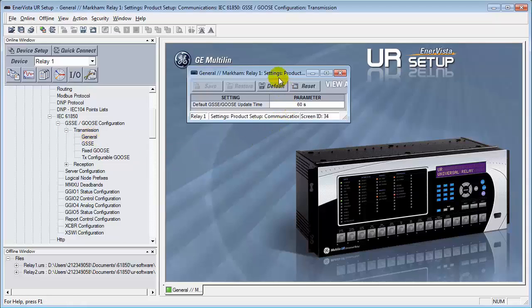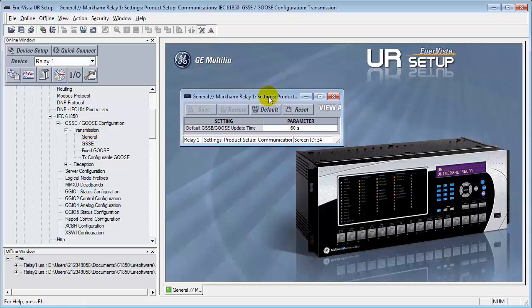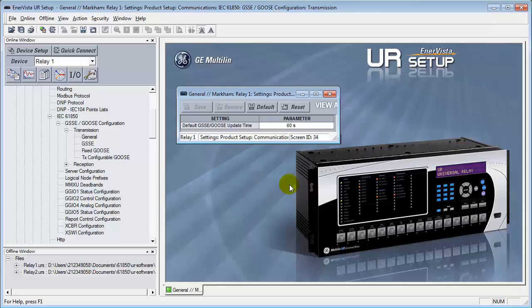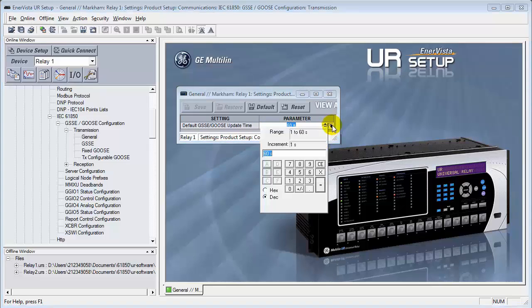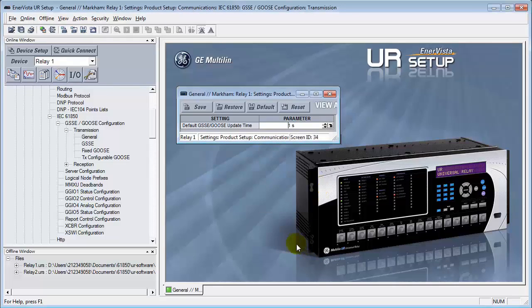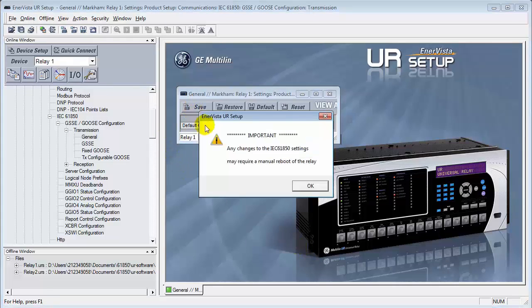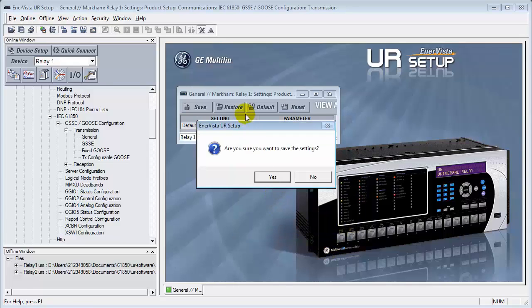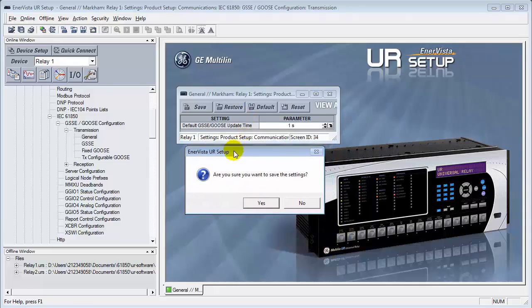This is how often we're going to update the information on the network if there's no change in information. The whole point here is that we do not publish any data onto the network unless there's a change in state or we exceed a specific dead band in the analog signals. So that we don't bombard our network, this is how often the information will be updated. This is adjustable between 1 second and 60 seconds. For our application here, let's reduce it down to 1 second. We'll save that. Verify it. So we'll have an immediate response as to when we do a change. Let's save that into the relay.